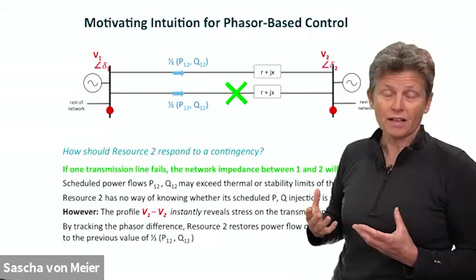So that buys time for someone who's actually doing an optimal power flow calculation to say, all right, the topology has changed, we now have reallocated power flows. We're no longer economically optimal because maybe this resource just kicked in a bunch of power generation that was quite costly. So a supervisory controller that has information about costs can then do a calculation to reallocate and choose new set points, issue new targets based on the new network condition.